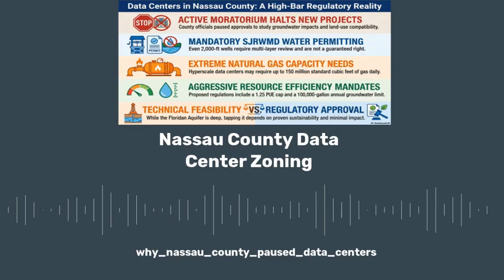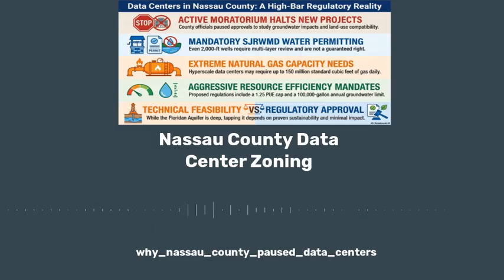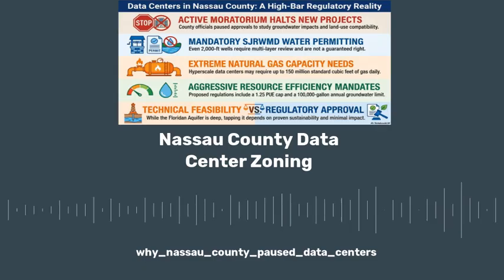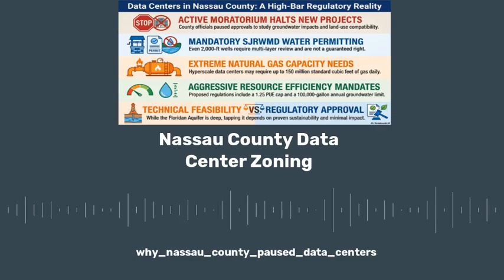To understand the gas demand, we first have to understand the electrical demand. Data centers are rated in megawatts. Historically, a 10 or 20 megawatt facility was considered large. Today, tech companies are proposing 100 megawatt, 500 megawatt, and even 1 gigawatt on-site power plants. Let's look at the baseline: say a data center wants to build a 100 megawatt on-site natural gas plant just to power its own servers. How much physical natural gas does that require every single day? A highly efficient 100 megawatt gas-fired power plant requires roughly 10 to 15 million standard cubic feet of natural gas per day. In the industry, they abbreviate that as MMSCFD.